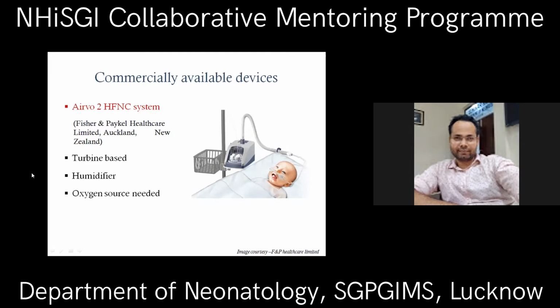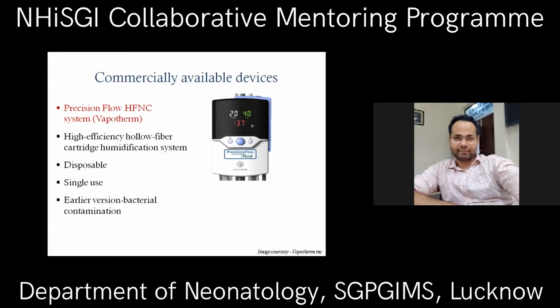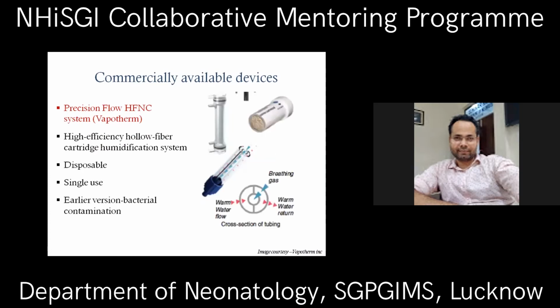Various commercially available devices are there in the market. Most commonly used in our NICU is the Airvo 2 HFNC system. It is from a company in New Zealand. It's turbine based and has a humidifier, and an oxygen source is needed. It is a high efficiency hollow fiber cartridge humidification system. As you can see, this is the cartridge, and the air flows through this, and there is circulating water which causes the humidification. It is disposable and single use. Earlier it was withdrawn because of the risk of bacterial contamination, but now it has been reintroduced in the market.